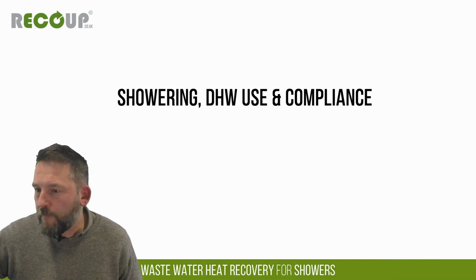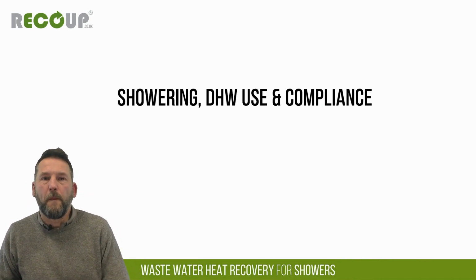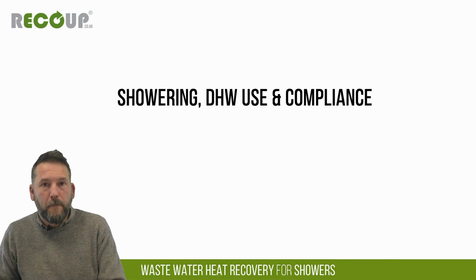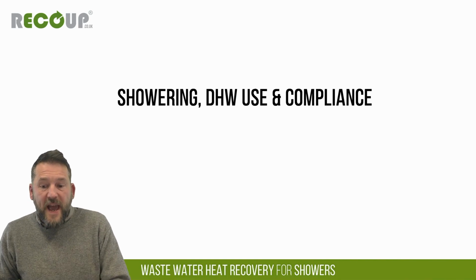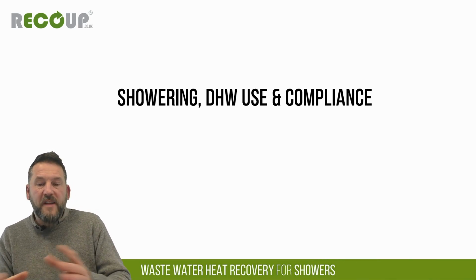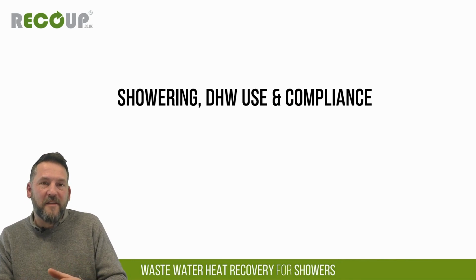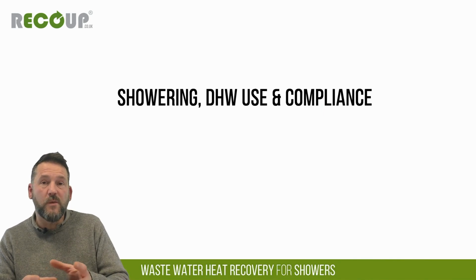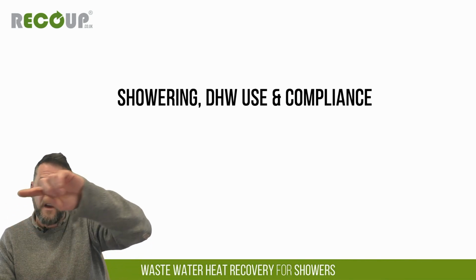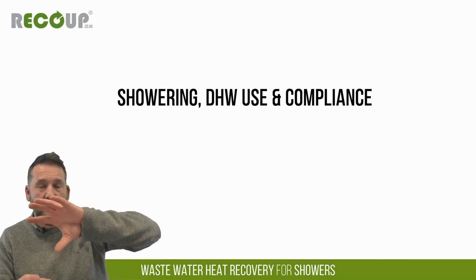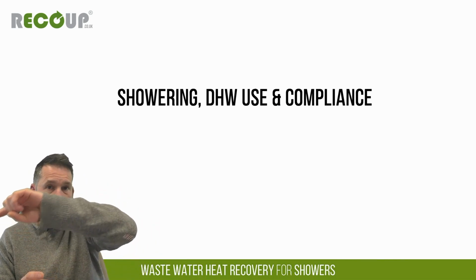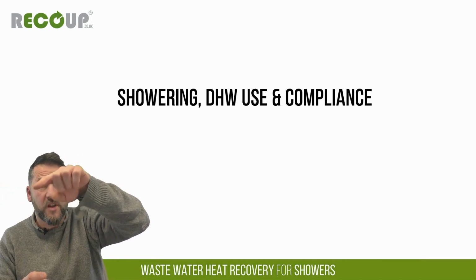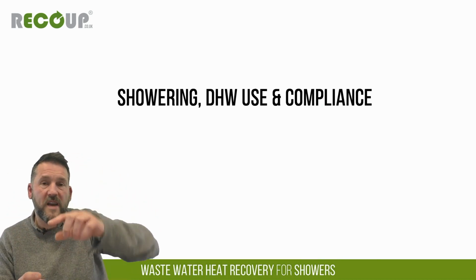Hi, Alice. There's just one question on the potential for blockages in the heat exchanger units, but I think you've kind of covered some of that. Yeah. So by design, we're designed not to block, and certainly taking the pipe as the example, it's a 50mm internal diameter pipe, so it's actually wider in diameter than the most standard plumbing waste pipe. The turbo rotator again is just an internal diameter of the pipe, so there are no mechanical parts in there. It's a twisted pipe essentially, used just to direct the flow of waste.